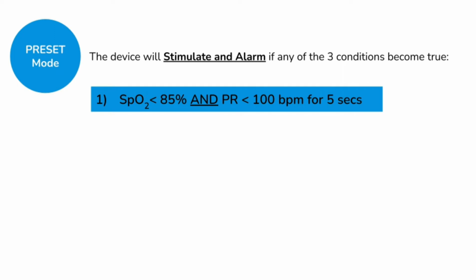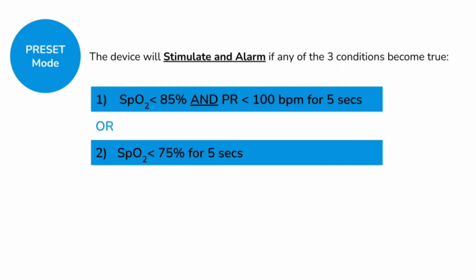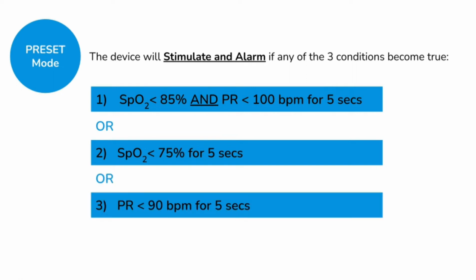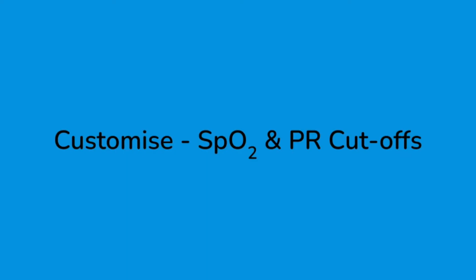1. The SpO2 is less than 85% and pulse rate is less than 100 bpm for 5 seconds. Or the SpO2 is less than 75% for 5 seconds. Or the pulse rate is less than 90 bpm for 5 seconds. These settings can also be changed as desired. You can customize at what SpO2 and pulse rate cutoffs the device will stimulate and alarm.